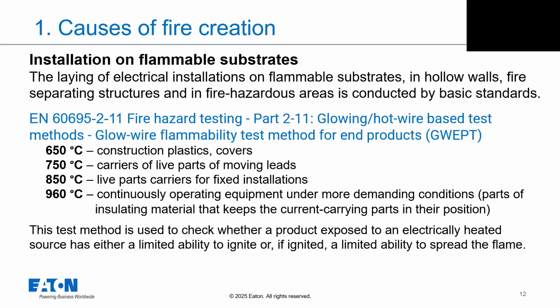A second option can be the use of inert gases, but this is very expensive and in the end not used. So the main focus of customers is: if we want to dramatically increase safety in switchboards, let's focus on selection of proper materials, proper insulation of cables, correct initial and periodical verification of connections - meaning torque of each terminal - and as the last, most expensive option, install smoke detectors, but not more. This is our experience from Europe and the Middle East.